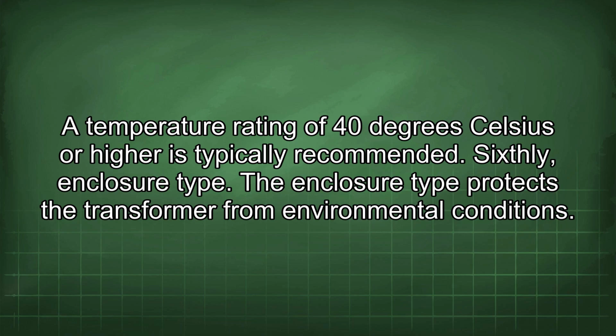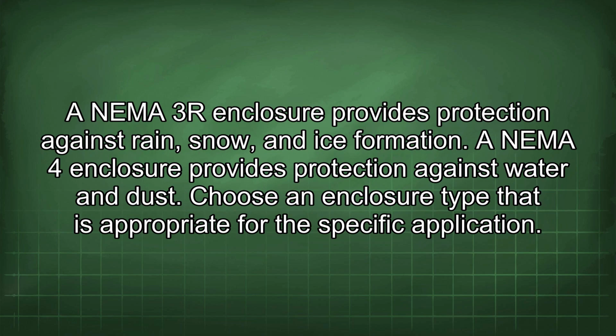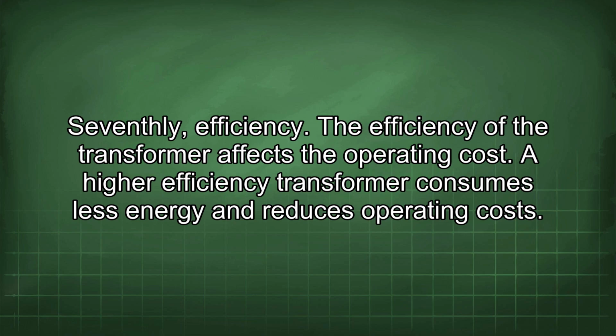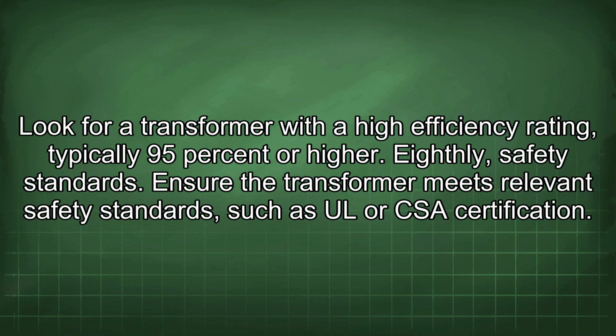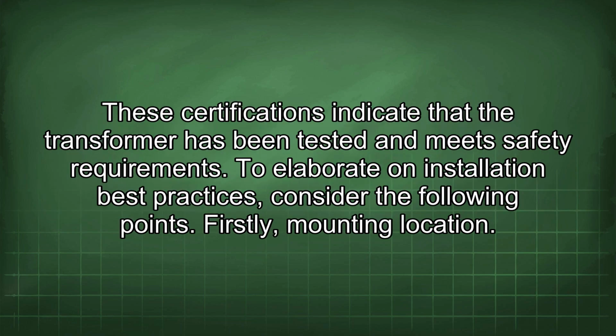Sixthly, enclosure type. The enclosure type protects the transformer from environmental conditions. A NEMA 3R enclosure provides protection against rain, snow, and ice formation. A NEMA 4 enclosure provides protection against water and dust. Choose an enclosure type that is appropriate for the specific application. Seventhly, efficiency. The efficiency of the transformer affects the operating cost. A higher efficiency transformer consumes less energy and reduces operating costs. Look for a transformer with a high efficiency rating, typically 95% or higher. Eighthly, safety standards. Ensure the transformer meets relevant safety standards such as UL or CSA certification. These certifications indicate that the transformer has been tested and meets safety requirements.